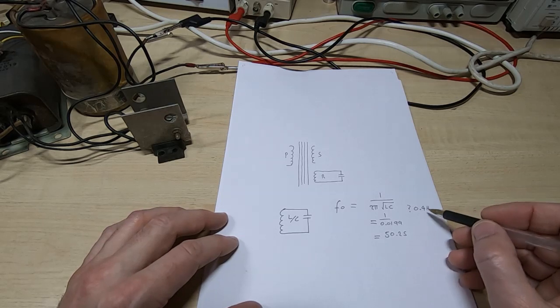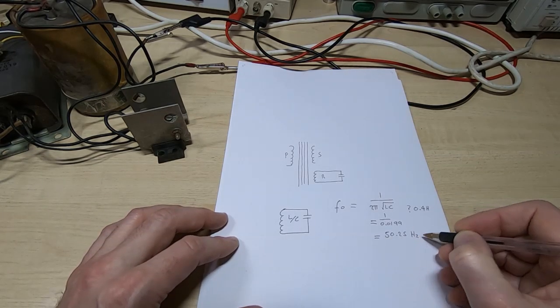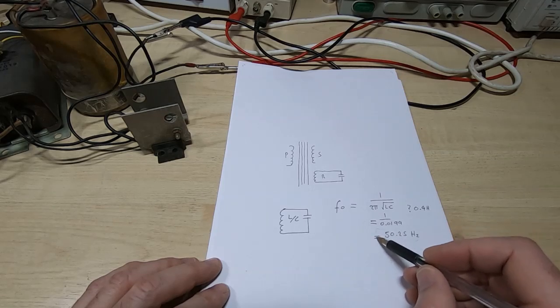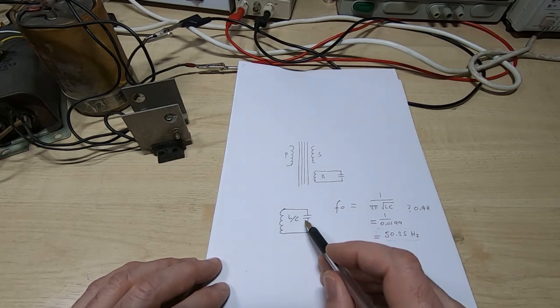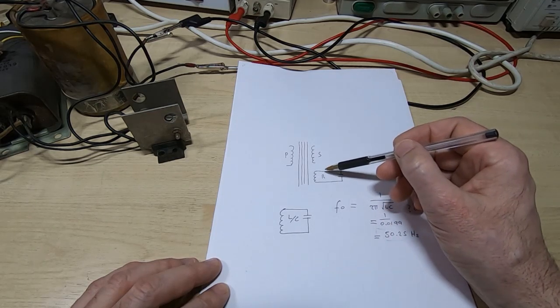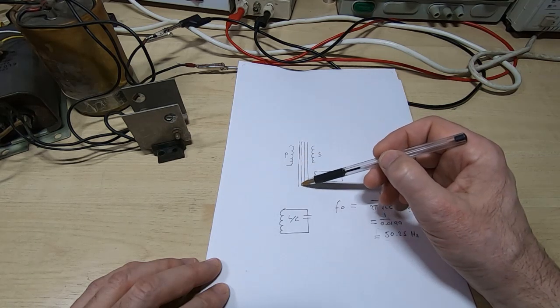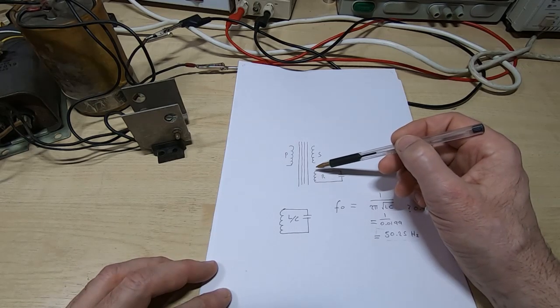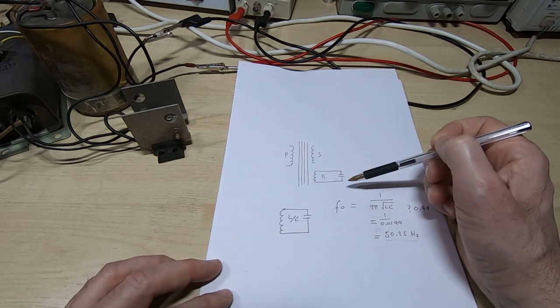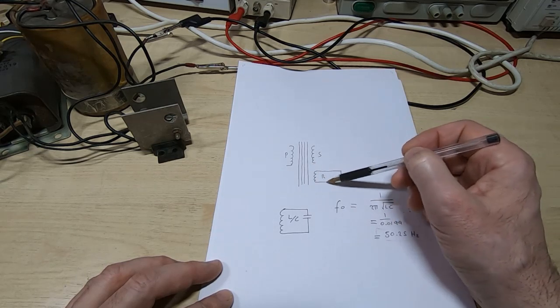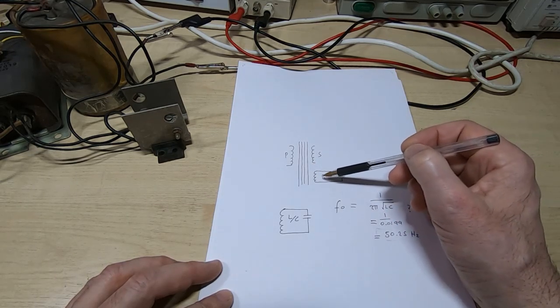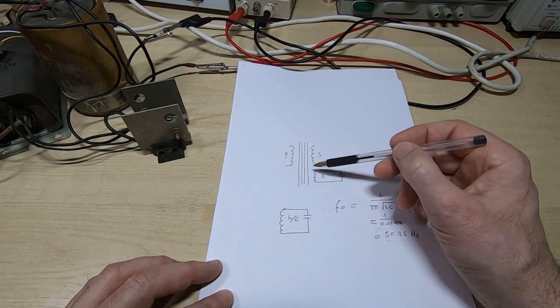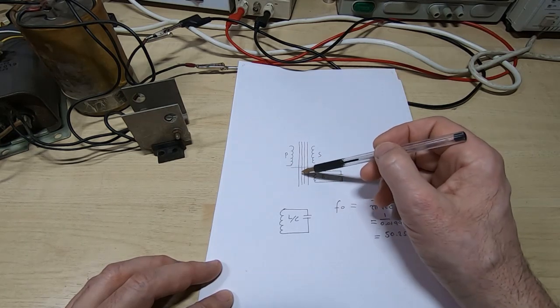OK, so that's a fairly good approximation. We've come out at 50.25 Hertz. And it's going to be somewhere between 50 and 60, I would guess. But it will be somewhere in this ballpark figure. It's this kind of frequency that we're aiming for. And of course, what we're aiming to do here is have this circuit resonate at 50 Hertz. So when it's given a driving signal through the core flux at a 50 Hertz or 60 Hertz rate, bear in mind that these transformers are very sensitive to frequency for what I'm hoping are becoming obvious reasons, then the idea here is that this circuit will resonate. And it's this back and forth current flowing through this winding that is causing the secondary part of the core to be driven into saturation.